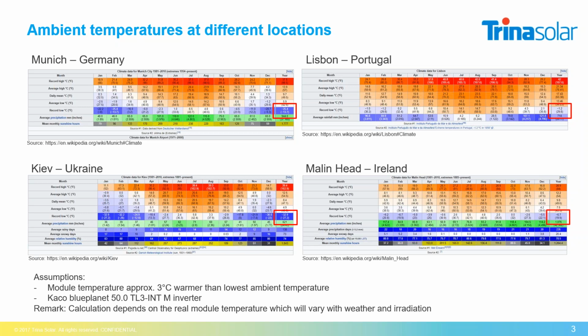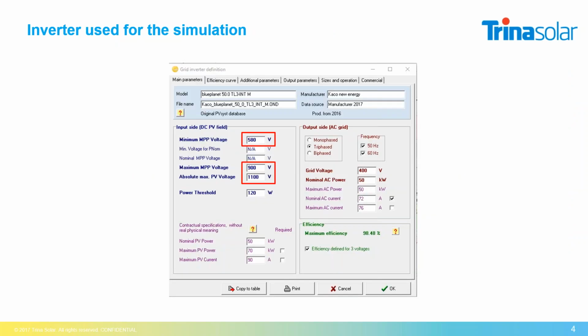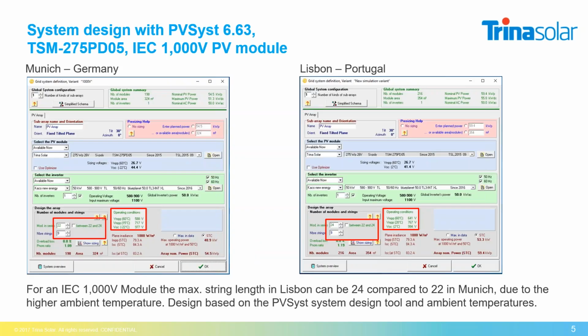And this will be shown in the webinar today, what is the impact on the different locations. Here we speak about the inverter. The inverter has an MPP range from 580 volts up to 900 volts, and the absolute maximum, the VOC, the system voltage for the inverter, is 1100 volt. What is also getting important for the further analysis.